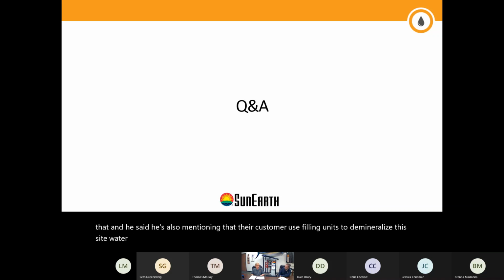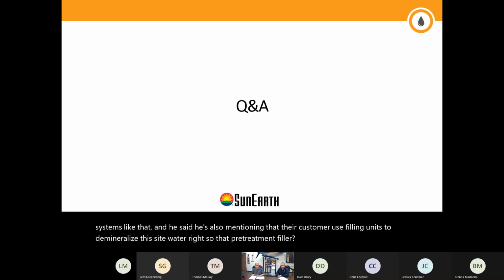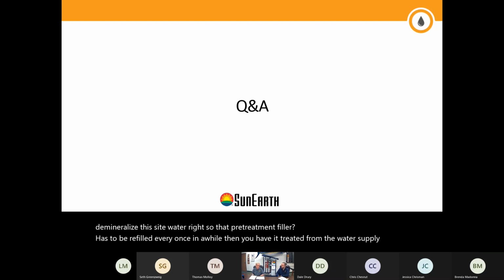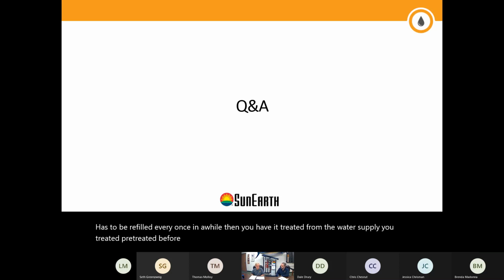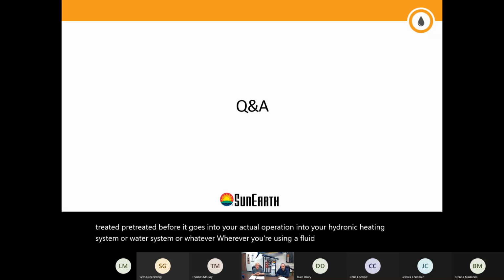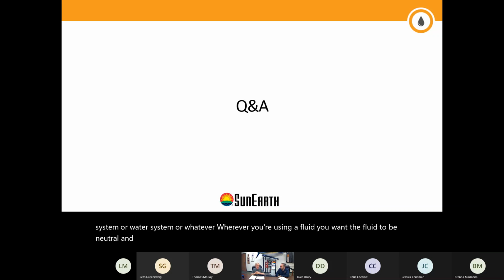Right, exactly - pre-treatment. The point-of-use filling: if you have a system that needs to be refilled every once in a while, you have it treated from your water supply. You pre-treat it before it goes into your actual hydronic heating system, water system, or whatever fluid system you're using - you want the fluid to be neutral to all, or as many of the components you have, as possible.